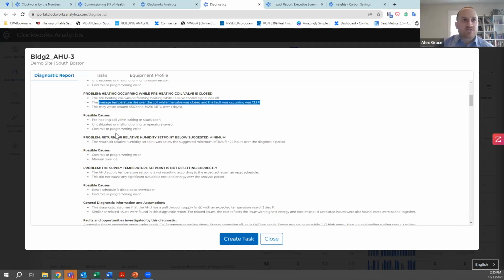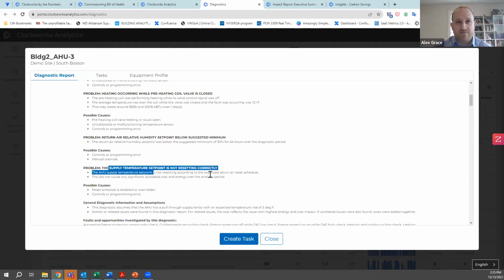And we want to direct resolution pretty quickly. So, problem statements, possible causes - I'm picking a few here to focus on rather than going through them all. We have issues on relative humidity, on supply temperature set points. We're not resetting, so we want that set point to be modulating based on, in this case, the return air conditions. There's an expected return air reset schedule - that's a common energy conservation measure.